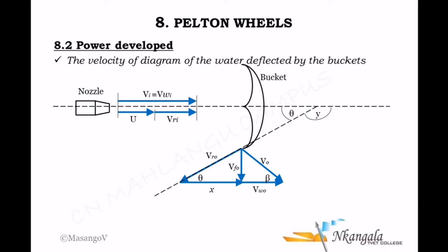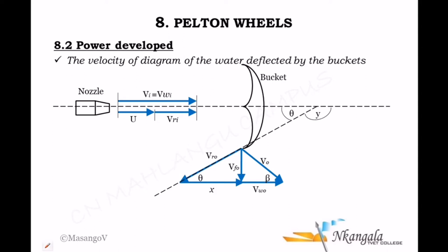In calculating the power generated, we start with the velocity of the jet coming horizontally from the nozzle. Since the jet is horizontal, the actual velocity equals the horizontal component with no vertical component. The buckets move with velocity U, which is the mean blade speed. The relative velocity is therefore the jet velocity minus the bucket velocity, since the water is pushing the buckets, the buckets must have a smaller velocity. The water is then deflected at an angle theta, called the deflection angle.